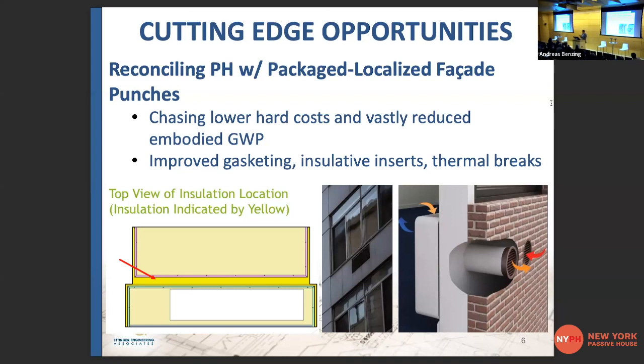There are kind of two approaches to this. The picture on this side is coming out of Italy — there's an Italian consortium looking to modernize the PTAC such that instead of this 42-inch by 16-inch punch in the facade that is the traditional PTAC, manufacturers have found a way to deal with all the process air that a PTAC needs for heating and cooling an apartment in two 6 to 8-inch round holes. So that's one way we're starting to limit the thermal bridge through the facade, limit the infiltration and exfiltration that can happen, and the lack of insulation that occurs at this punch.